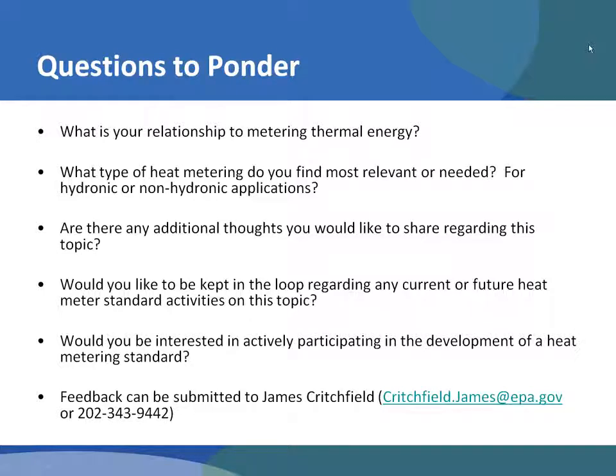Good question. First, we need to get back to which technology we're talking about. With a dual transmitter, I'm assuming that we're talking about a differential pressure style of meter. I mentioned that with a differential pressure meter, the relationship between the measured variable, which is differential pressure, and flow is actually a square function, which limits the amount of turn down that you can have. With the dual transmitters set up, you can actually have two different ranges, butt them up to each other, so to speak, and that's a way of getting much better turn down and low flow capability out of a differential pressure style of meter. So again, that's one way of approaching it. The multivariable aspect of that, I'll have to defer. We are not a manufacturer of differential pressure meters, so I don't know that level of detail.